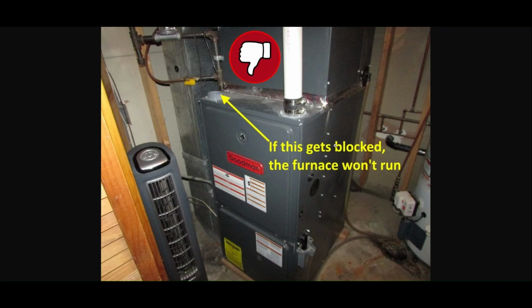So this picture that I just pulled off online is just saying that debris can go right down in there. You're supposed to put a twin elbow on top of this. So let's be clear, the manufacturer allows you to do this as long as there's enough combustion air in the building. And I'm not going to get into that. Most buildings nowadays are pretty tight, so you're pushing it and you put the building under negative pressure, which affects other appliances like this water heater behind there. But for our intents and purposes, my biggest beef with this is it's not that expensive to do. You have to drill another hole to the outside, but what it prevents is debris from inside the house getting into the combustion chamber, which ends up wrecking the heat exchangers on furnaces much quicker.